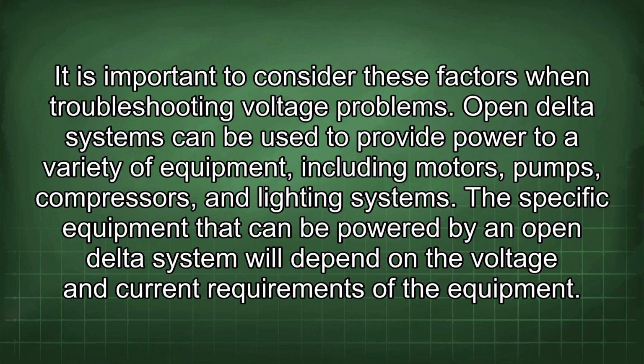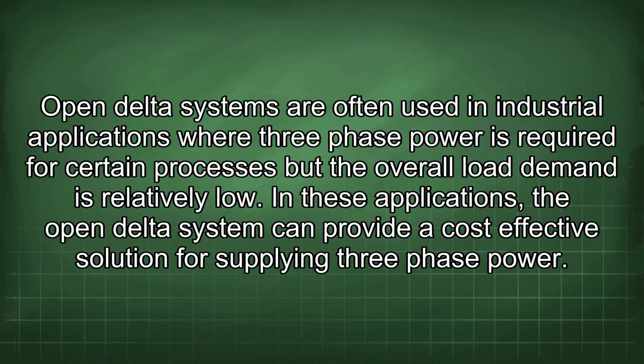Open delta systems can be used to provide power to a variety of equipment, including motors, pumps, compressors, and lighting systems. The specific equipment that can be powered by an open delta system will depend on the voltage and current requirements of the equipment. Open delta systems are often used in industrial applications where three-phase power is required for certain processes but the overall load demand is relatively low. In these applications, the open delta system can provide a cost-effective solution for supplying three-phase power.